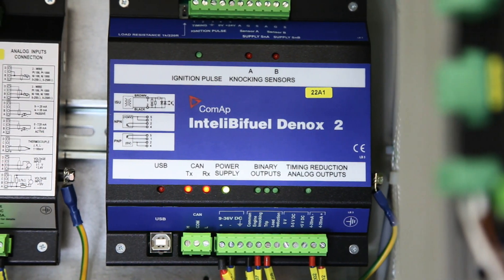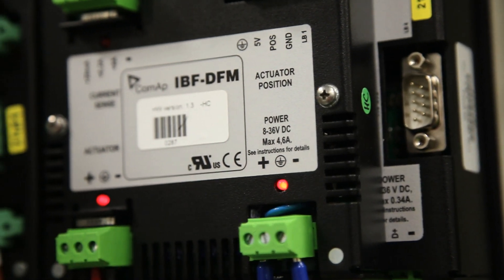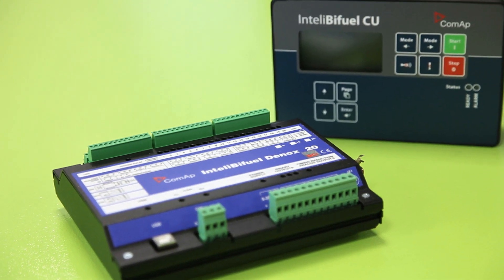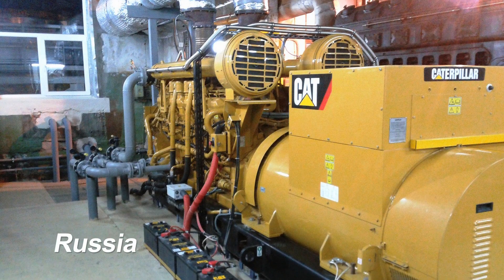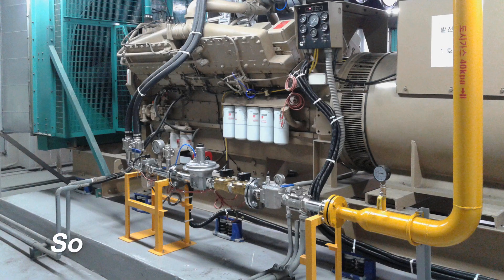The COMAP D-Knock system acts very fast to back off the gas supply if there is any hint of knocking. This protection is unique to the COMAP system. Quality, fully automated bi-fuel solutions, like COMAP's InteliBifuel, ensure that all key engine safety parameters are met at all times. Should any engine parameter move towards a maximum limit, the amount of gas will automatically decrease.